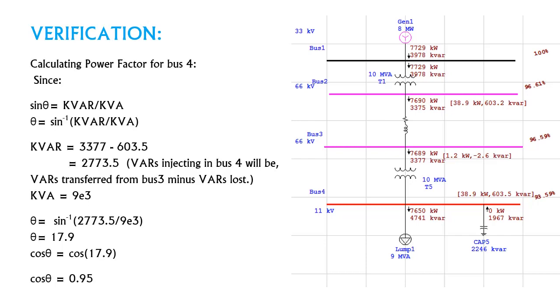Now this is the most interesting part, whether what we calculated is actually working or not. So again calculating the power factor, whether the power factor has increased to 0.95 or not. So using the same formula and again calculating the kVARs in the same manner. And now again calculating the theta and taking the sine inverse and again taking the cosine of the theta and we get 0.95.